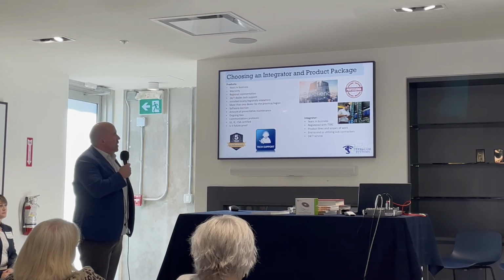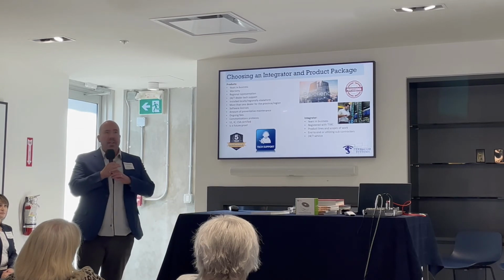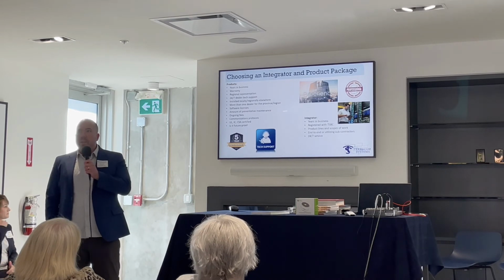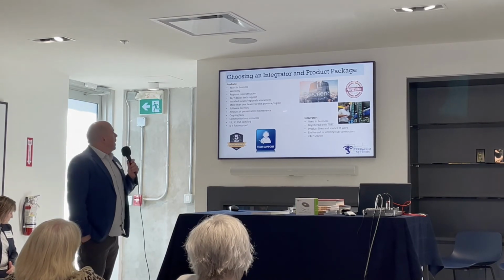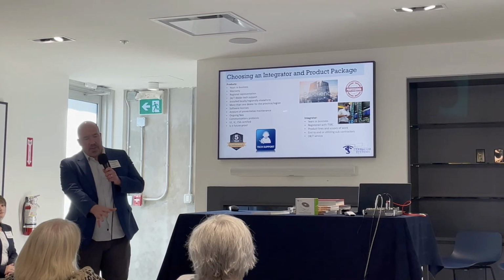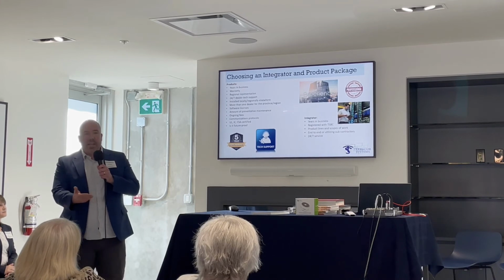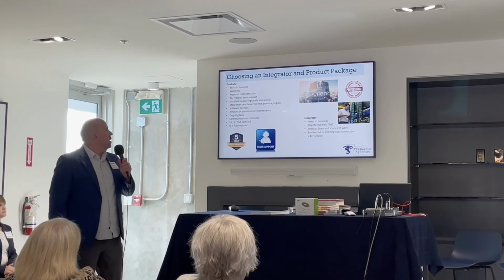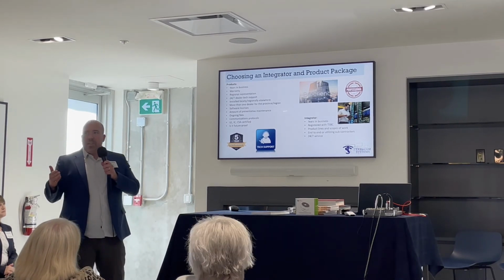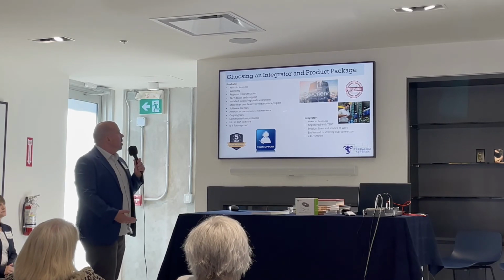Making sure that this particular system has been installed elsewhere in the region. Sure, maybe they have hundreds of installs in Quebec, but is there actually an install here in BC? More than one dealer for the product? Are you stuck with just this one integrator? Maybe you had a falling out or you felt they weren't giving you good service, or do they allow other dealers to carry this product line? Software licenses, how much do they charge ongoing? That's one thing that you have to budget, ongoing software licenses, ongoing fees, and do they have the proper certifications?